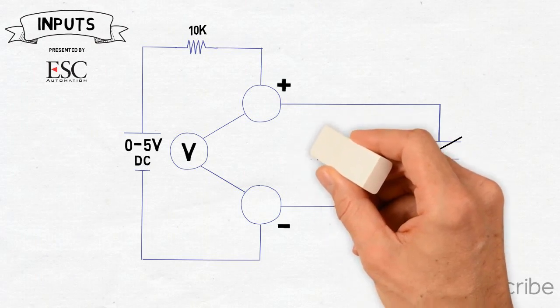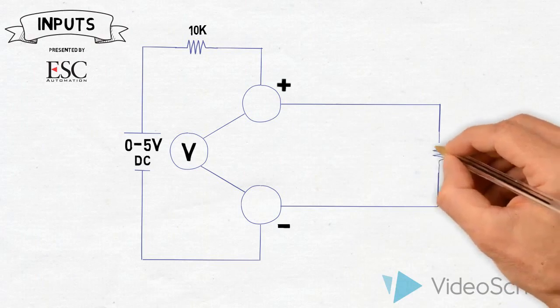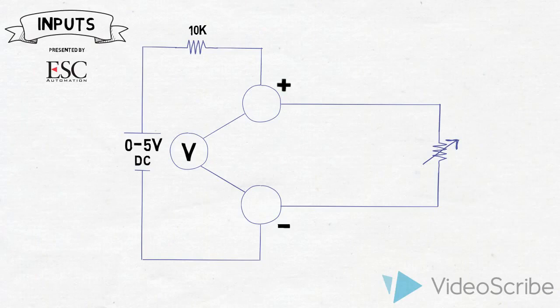We transmit that as being on and off through a voltage reading on the panel. When you measure temperature, a temperature sensor is basically a thermistor—a resistor that changes according to temperature. As temperature rises, resistance goes up. As temperature drops, resistance goes down. As resistance changes, so does the voltage drop. The panel reads the voltage drop across the thermistor and converts it to temperature through a scale range.